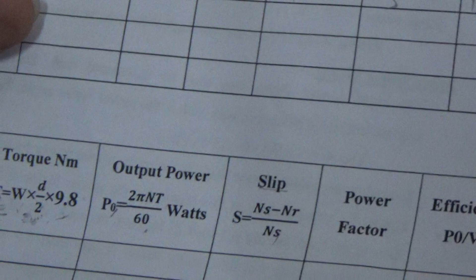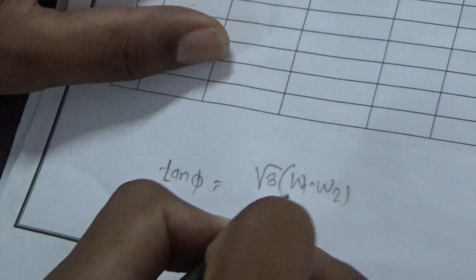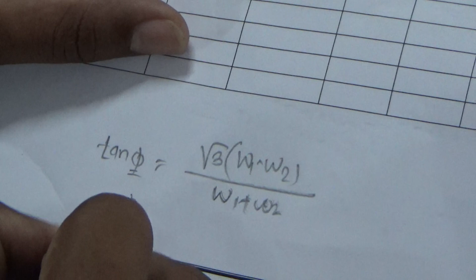So how we will calculate the power factor? The power factor calculation formula is very simple. As we know, tan phi is equal to root 3 times W1 minus W2 divided by W1 plus W2. With that we can easily find phi, and once phi is available, we can go for cos phi.